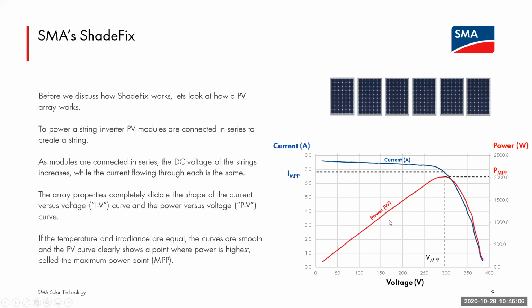So this is a simple IV curve. It goes up and down based on the irradiance, right? So if you have good full irradiance, the current will be high. If the irradiance goes down, the modules can only output maybe a lower current or a lower power. But what the module gives our inverter is what we can choose to make energy with. If there's an optimizer behind a solar module and the module is totally shaded, whatever the module can give that optimizer is what that optimizer can use. So optimizers do not magically make power. It always starts here at the foundation, which is what's the voltage and current that the module is giving to us to use.